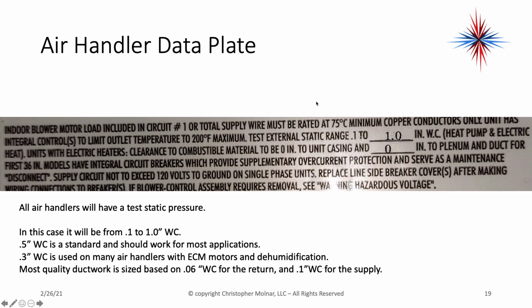Also on the air handler data plate, there's a static pressure. On this air handler, it's a range, 0.1 to 1.0. That's a very wide range. Most often, you're going to find a single number, which is the maximum static pressure. A lot of times, 0.5 inches water column is standard. 0.3 is used on many air handlers with ECM motors and dehumidification. Most quality ductwork is based on 0.06 for the return and 0.1 for the supply, which gives me 0.16 on the ductwork side.